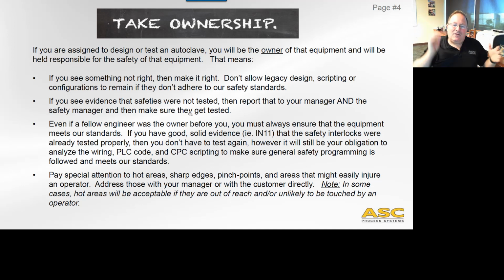What that means is that if you come in at the end of a testing phase and you're going to be the one to finish testing, it's your obligation to make sure that the first engineer did things safely and correctly. If you have good solid evidence, via, let's say, an IN11, that the safety interlocks were tested properly, then you don't have to test again. However, it will still be your obligation to analyze the wiring, the PLC code, and the CPC programming and scripting to make sure that those meet our current standards. Just because there's an IN11, when you walk up to a piece of equipment, the first thing you have to do is check those three safety obligations. Bottom line is, when you take over testing, you're now the new owner, and you have to make sure that things are safe before you start.